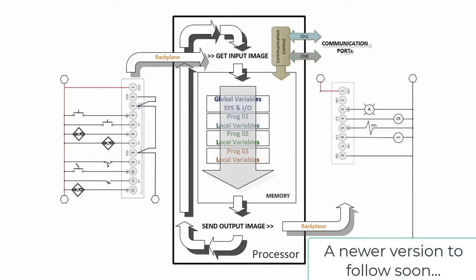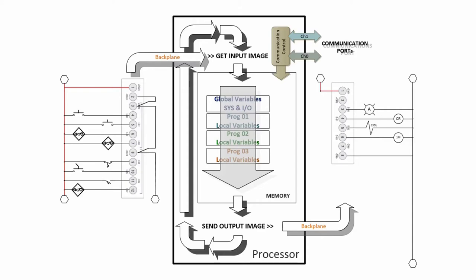Across the backplane we collect up the input image and store it in the global variables, then we execute the program changing the state of both global variables, outputs, and local variables. Each program can read any of the global variables but only the local variables of its own program. Program two can read and write to global variables and its own local variables, but it cannot see or touch anything in program one or program three. The output image is then sent out. With the Micro 800s, especially the 810, there is no real backplane — you cannot expand it. The 820, 830, 850, and 870 you can expand the I/O, so they do have a backplane even though it's encapsulated in the plastic box.